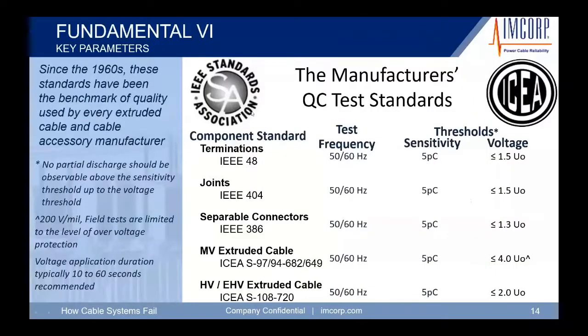Okay, so today these are our standards. IEEE 48, 404, 386 are for the accessories, and then ICEA standards for the medium voltage and high voltage cables. So we test, in the factory test, at 50, 60 hertz, what's used in the field today. Now, it's important to know that all cable accessories and cables have some sort of partial discharge in there. Now, is it more manageable?